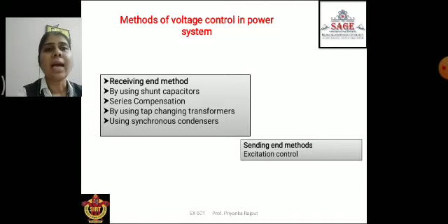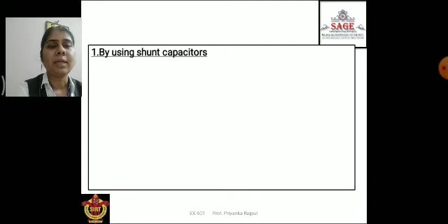As its name suggests, shunt capacitor means parallel capacitor. In the transmission line we connect a shunt capacitor for voltage control. During power transmission there are problems like poor power factor, poor voltage regulation, poor efficiency and less reliability. Shunt capacitor compensation is a method to avoid these problems. By using this we can get better performance and a better power system.